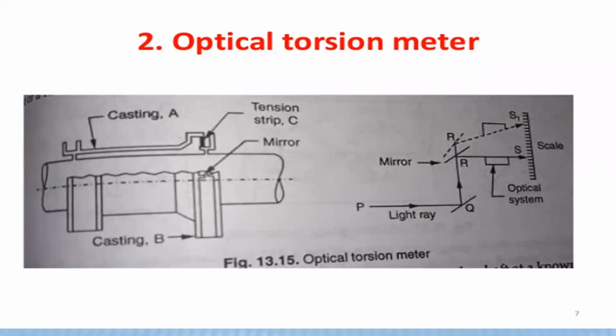So what is the main thing? Whenever the shaft rotates in the optical torsion meter, light passes through this casting, and the twisting moment occurs in this tension strip, and the light passes through the mirrors. There are two mirrors: light passes through one mirror and is reflected to the other mirror. The angular twisting moment is read on the calibrated scale. So that is how we measure the angular twisting of the ray by using these optical systems.